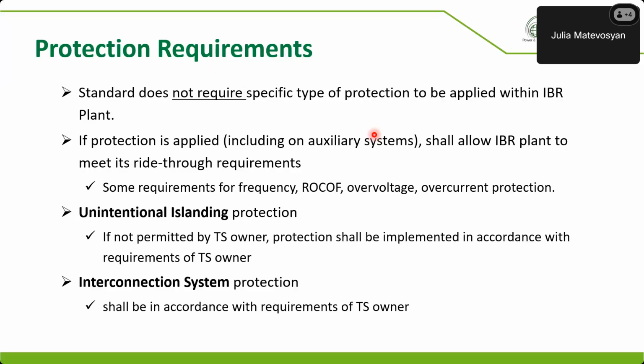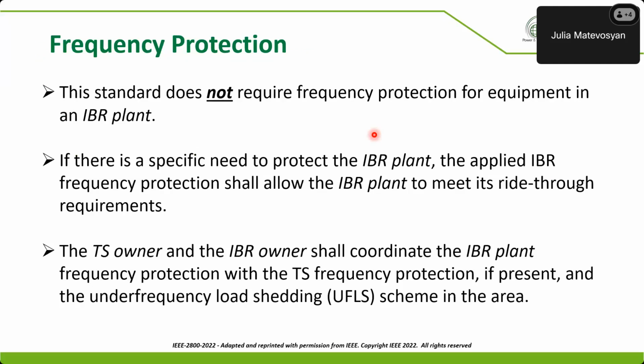All right, so I'll take you into a little more detail, but I think at the end of the next 10 minutes, you will feel that this first slide outlined expectations very clearly. So, frequency protection. As I mentioned earlier, unlike 1547, this standard does not require that the plant trips for some weird frequency deviation for some long time duration, right? If the plant needs to protect itself from frequency disturbance, then they just need to make sure that protection is set so that the IBR plant meets the ride-through requirements of the standard. And the last bullet is more of a reminder: make sure that any protection applied within the plant is coordinated with any frequency protection on the transmission system, such as the under-frequency load shed program usually implemented on transmission too. There is no point in tripping generation before tripping a load, right? So, very basic requirements there.